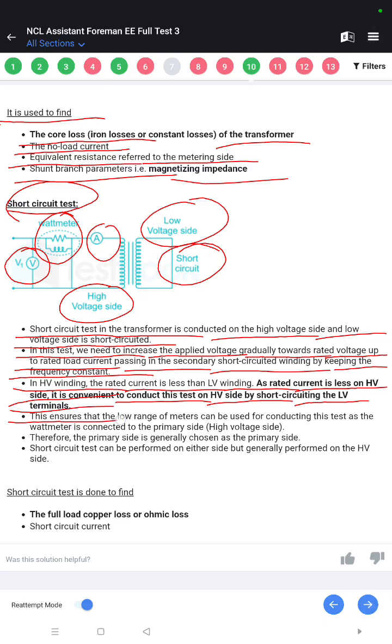This ensures that the low range of meters can be used for conducting this test, as the wattmeter is connected to the primary side, the HV side. Therefore, the HV side is generally chosen as the primary side. The short circuit test can be performed on either side but is generally performed on the HV side. The short circuit test is done to find the full load copper loss or ohmic loss and the short circuit current.